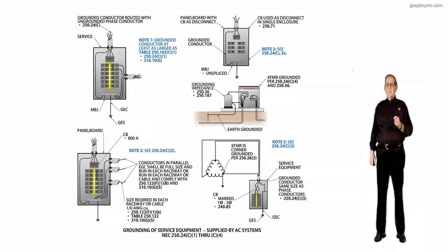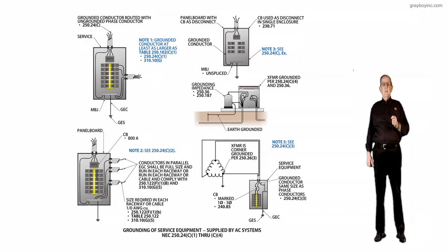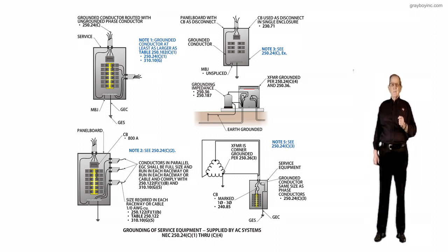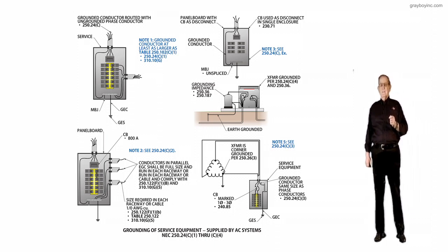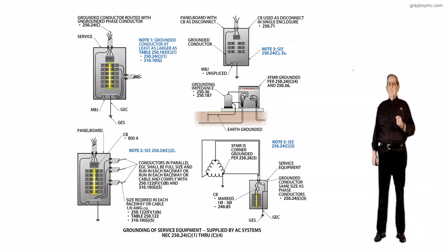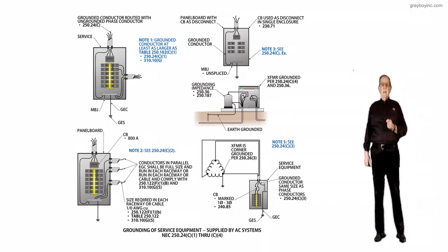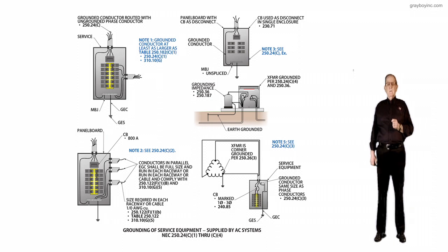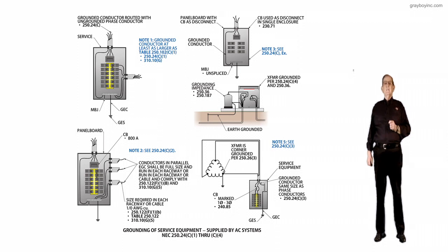Parallel conductors in two or more raceways or cables, delta connected services, high impedance grounded systems. Section 250.24 has been reorganized and restructured again to make it more usable and clarify the requirements in such a manner that we all can be on the same page. But now let's take a look at this.